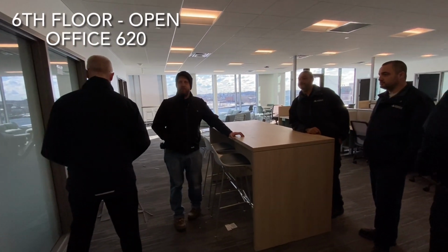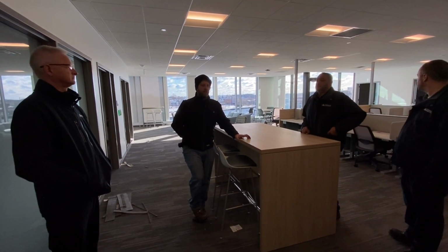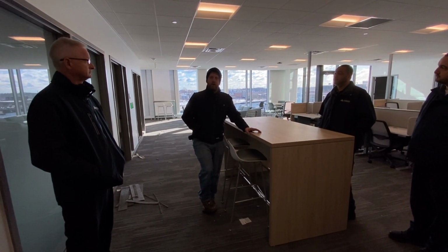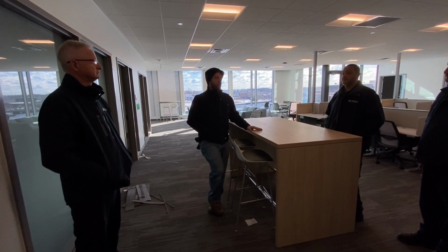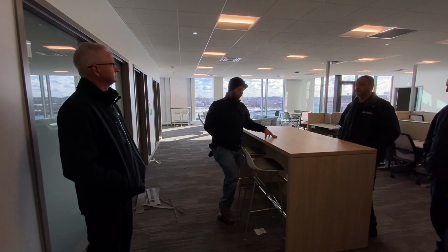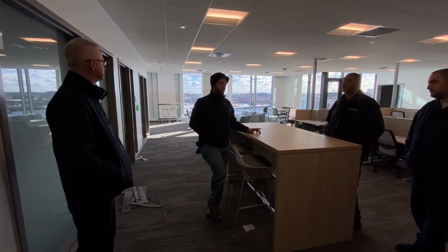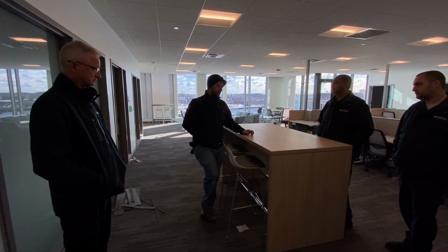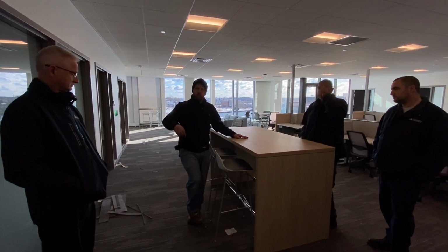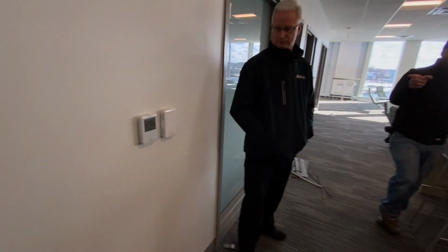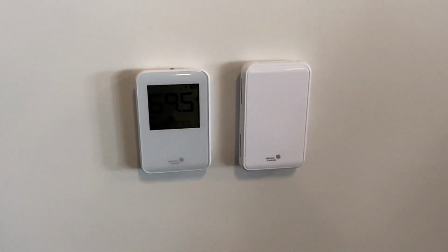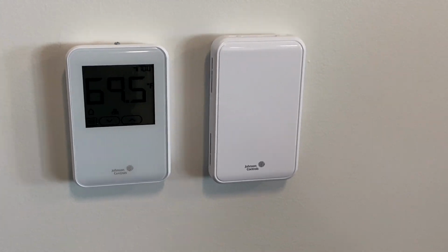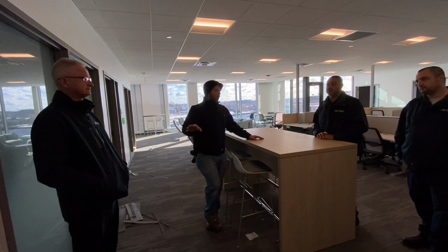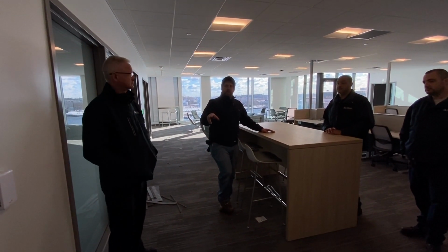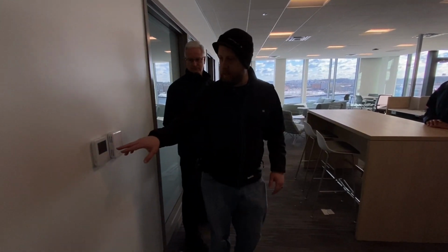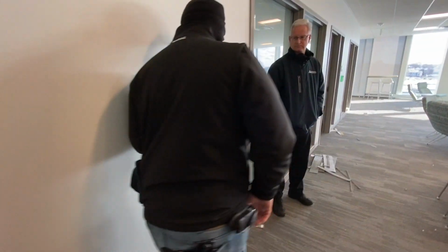So this is a typical non-lab space. This room is being fed from the existing rooftop air handlers, so this is taking the building air. And these are Johnson Controls. When I say Johnson Controls, these are our first-party controllers here. Those are a typical VAV box, just the standard rotating VAV. On the wall, we have our Johnson thermostat and a CO2 sensor. If the CO2 starts to elevate, we'll try to bring in more fresh air. We'll reset the minimum air from the VAV box up to get more fresh air in. Pretty much the big common areas have the CO2 device, and then we have control of the heating in this space. So, our standard JCI thermostat.